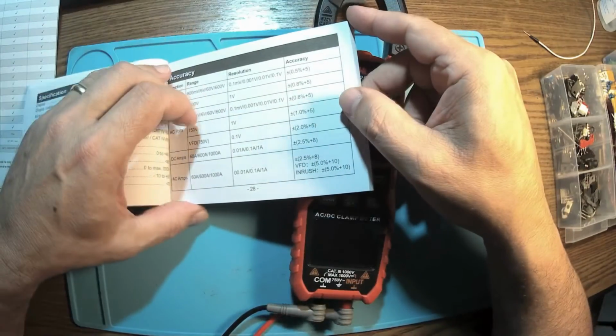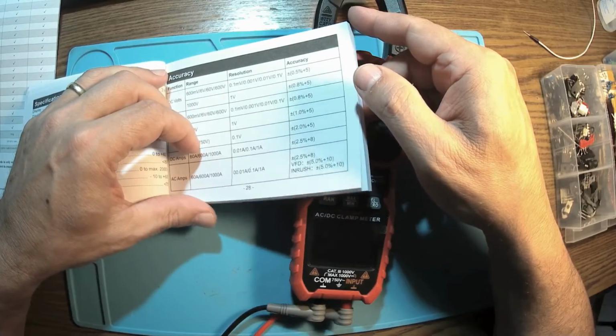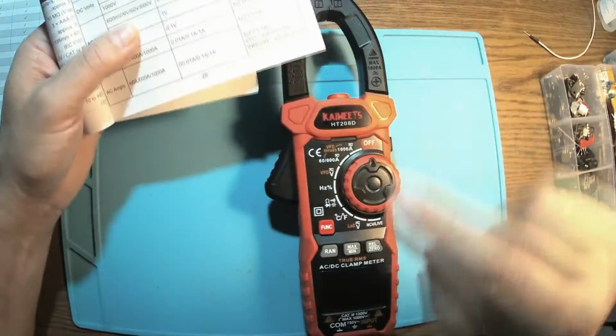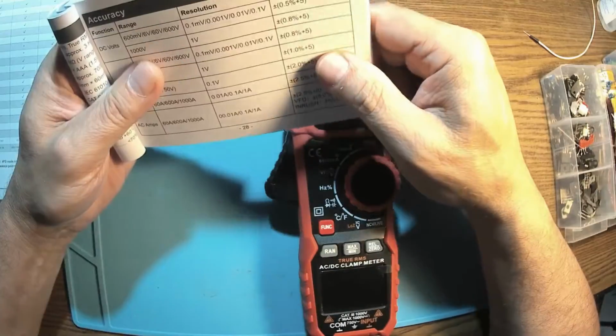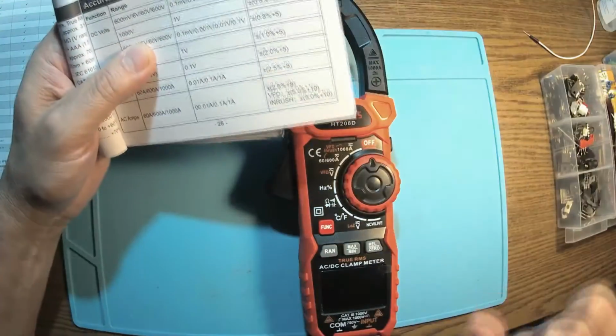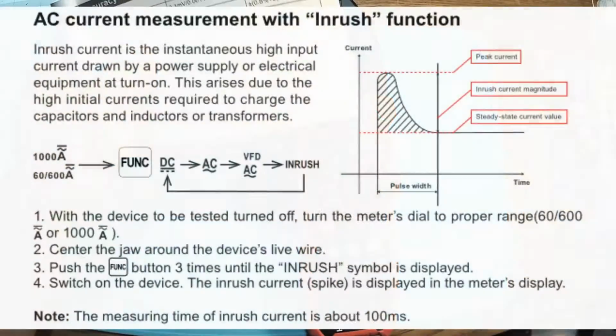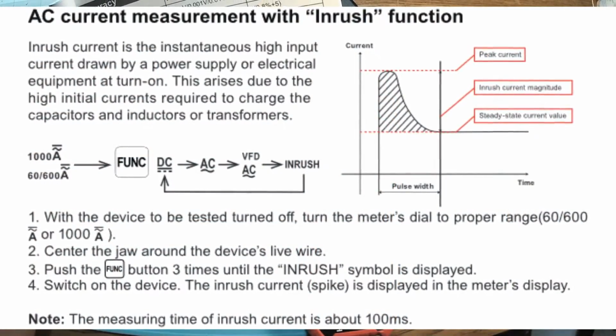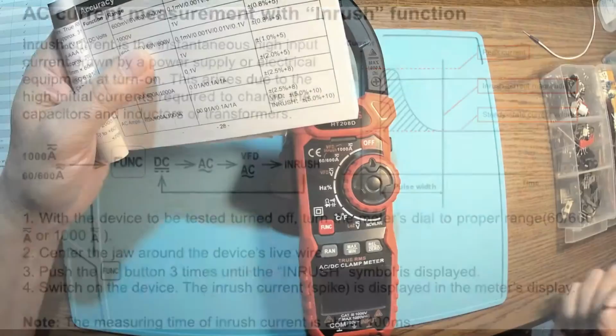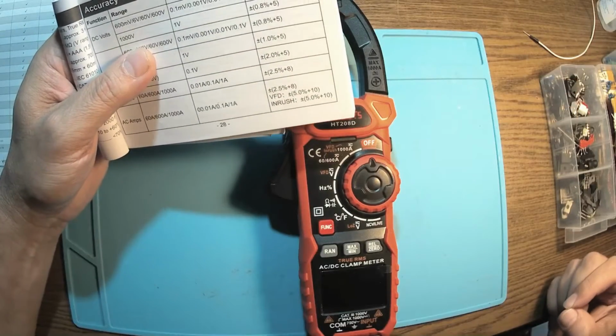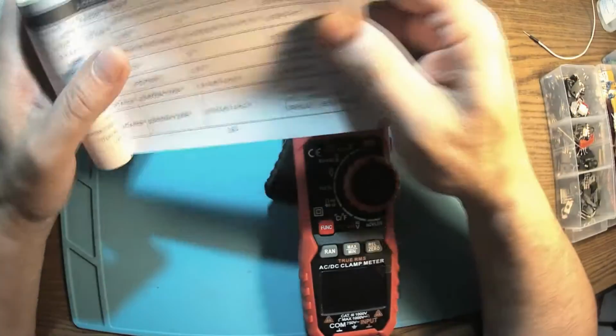Then, of course, DC amps, AC amps. Another nice function is the Inrush Current - this clamp meter is able to measure those very short peak currents, like a big motor in the moment when you plug it in, for a split second there is a huge amount of current. This one can measure that, meaning it's very fast at measuring it.